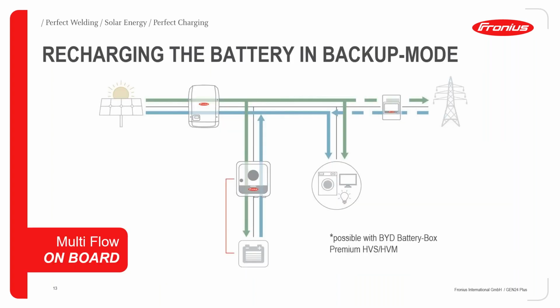With a BYD battery connected, it's also possible to recharge the battery in a backup scenario. As pictured here, if the grid fails on the right side, it's still possible to recharge the battery if the sun is shining, and we're able to supply our loads from the battery or from the PV modules even in backup mode.